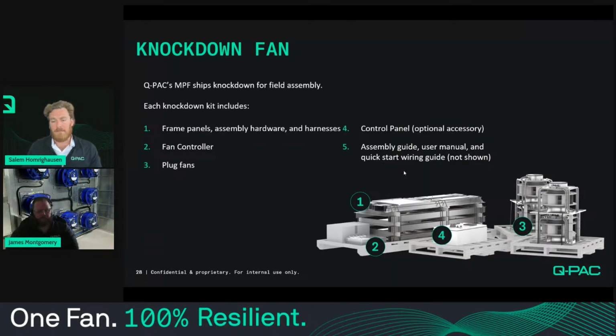So, back on those earlier slides, I showed you the first Q-PAC fan array that was out there in 2012. We built a palletized version in 2015, and the shipping and packaging of the product developed as well. So now it's laid out as you see in the slide here. You've got your frame panels, your assembly hardware and harnesses, all with the fan controller on the first pallet. Your control panel, if you have that, is going to be on the second pallet, and then your ECM plug fans will ship in stacks of 2 and any additional pallets.